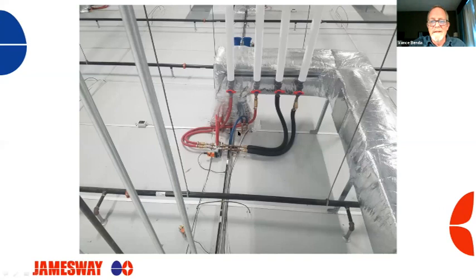All right, now this is your thermostat mounting location. This is a P120. And this is the middle of a P120 where the air comes in through this real nice air intake duct. So from here back would be the rear zone of the P120, and from here forward would be the front zone of the P120. And this thermostat is mounted right at the split between the two zones, which is the preferred mounting location.